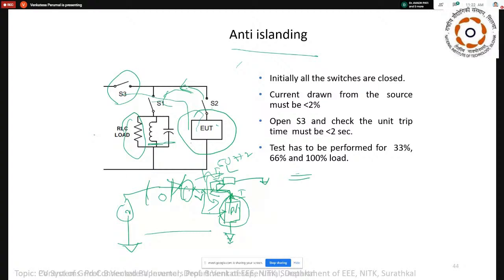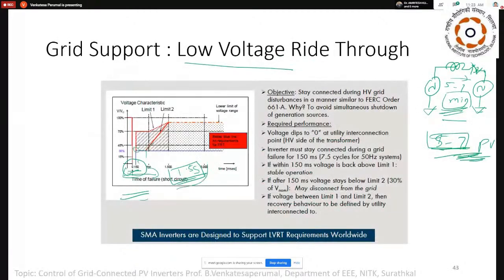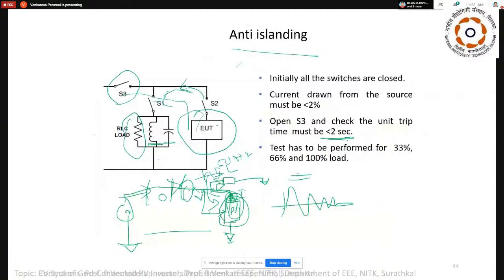How can I identify it? What people normally do is add a little bit of reactive power. After every 2 seconds, they will add one cycle of change in angle. This change in angle by the PV system won't take effect if the grid is there. If the grid is a big stiff system, the frequency won't alter. If I alter the PV generation frequency a little bit, I will come to know the grid is there. But if the grid is not there, altering the frequency will make the voltage die down from high voltage oscillation to low voltage. It has to be detected within 2 seconds. Looking at the previous slide, that was 1.5 seconds, and here it is less than 2 seconds.